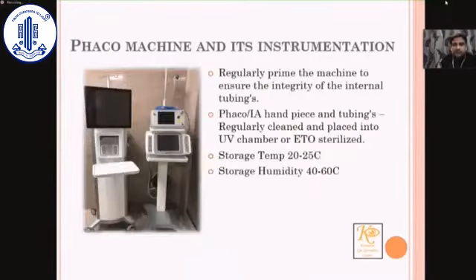The ultimate machines in our practice, the phacoemulsification or vitrectomy machines, need the most important care. These instruments have a lot of hollow devices, and special care is needed to maintain them. The handpiece should be cleaned as per the protocol and stored in a UV chamber, or it can be packed and kept in an ETO also. Ensure that the phaco machine is primed regularly and the foot pedal is checked for proper functioning. Adequately dry the hollow instruments before you store them. Also, note the room temperature at which the instruments are stored.